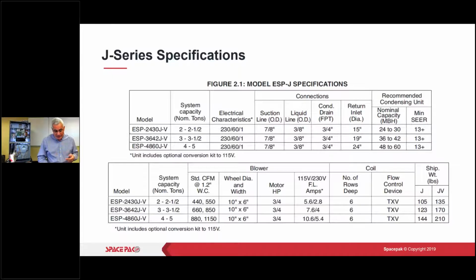So a question even came up last week, does it matter, my outdoor unit's going to be a really high SEER, does that add any value to the system? And the answer is no. Your standard SEER rating equipment will work fine with SpacePak. We are not affected by any codes or anything like that where the efficiencies have to be very high. It's a different type of system. It's not conventional, nor is it a split system.